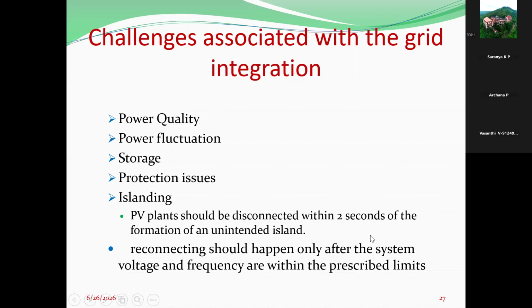Then comes the islanding problem: the PV plant should be disconnected within 2 seconds of the formation of an unintended island, otherwise the whole system gets affected. Reconnection should happen only after the system voltage and frequency are within prescribed limits. This islanding issue is a major concern that we have to take care of.